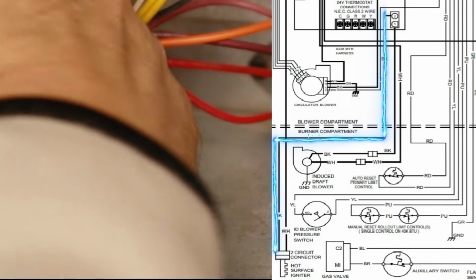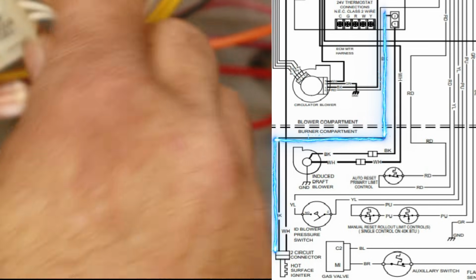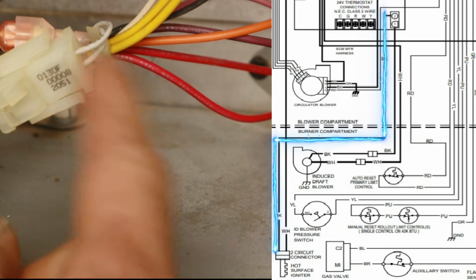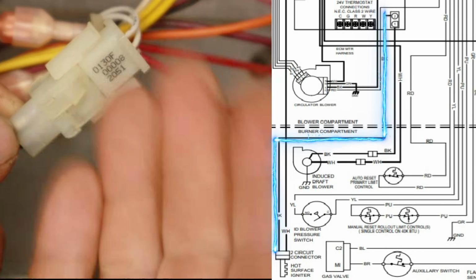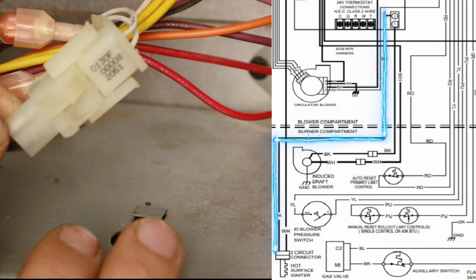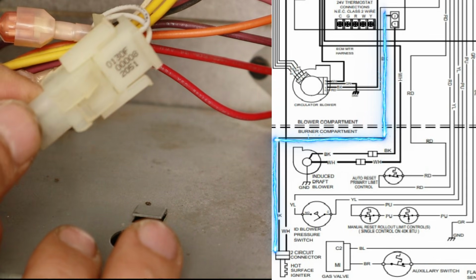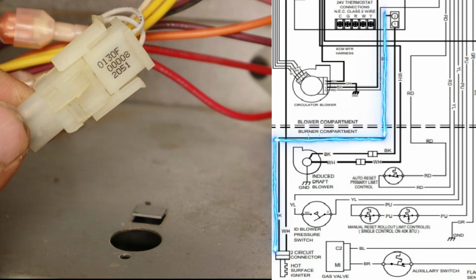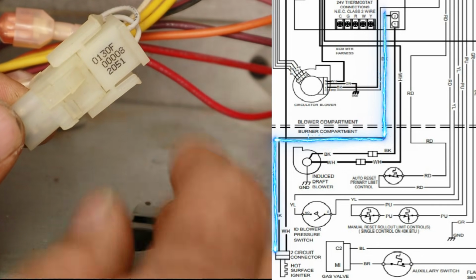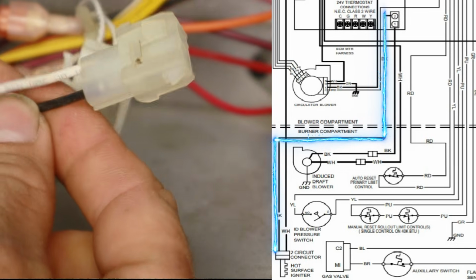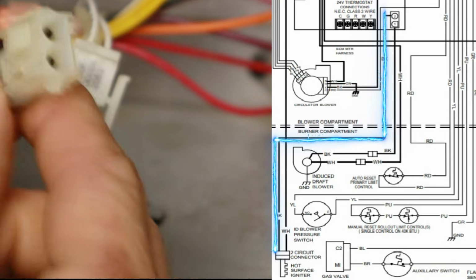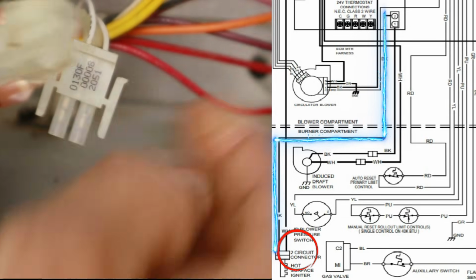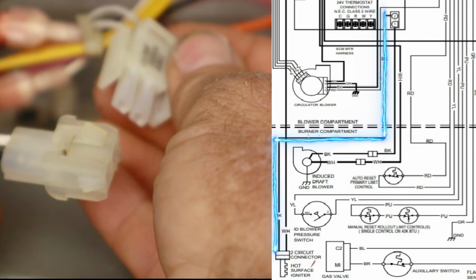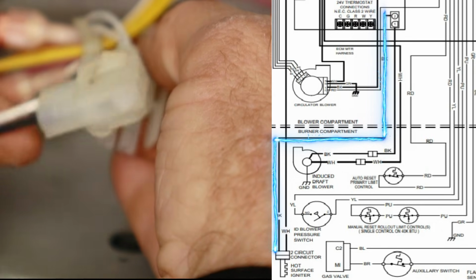Now when I pull that wire up, you can see we have a connector right here that goes into our hot surface igniter. So if I go this far into the sequence and my hot surface igniter is not lighting up, to make sure my control board is actually sending power to it, I can disconnect this plug and test to see if I have 120 volts going to that plug that feeds the hot surface igniter. The reason this is done is that if you ever do have a bad one, you can easily change it out without going through all the wiring going back to the control board.